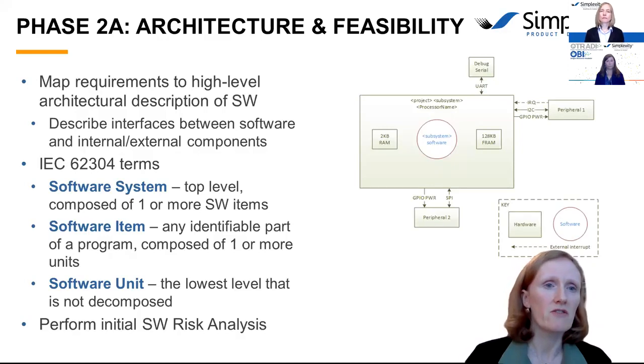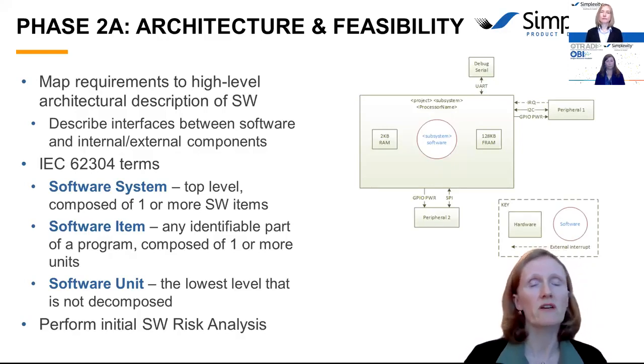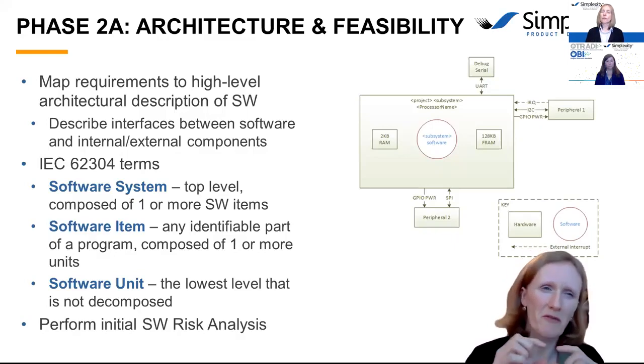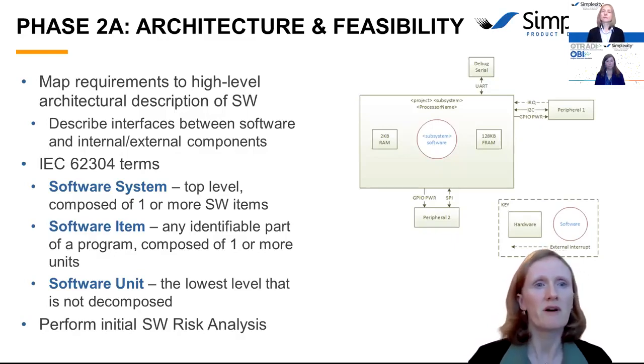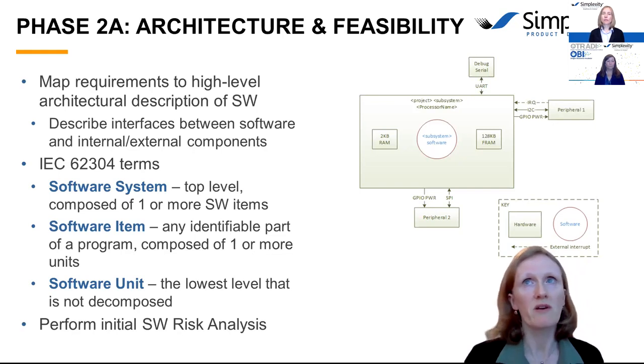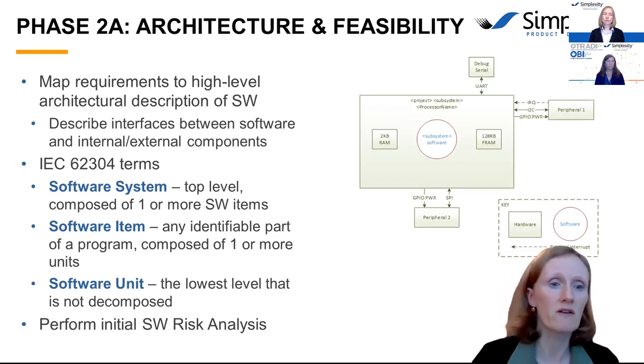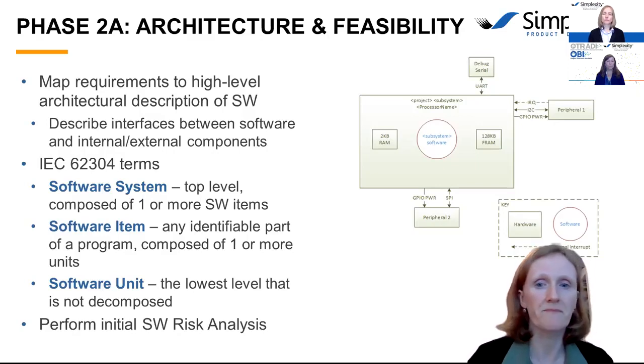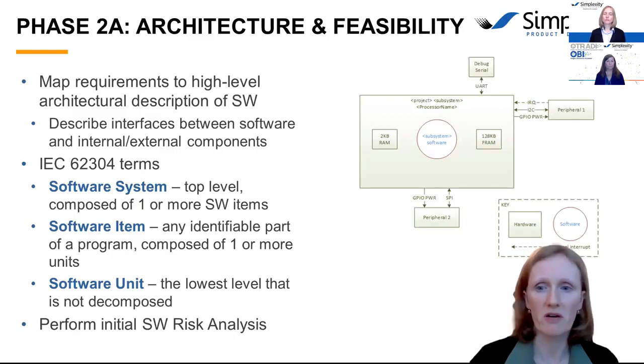But it can get a little confusing because a lot of times in the software industry, we talk about unit testing and we're talking about function-level testing. But for medical devices, the software unit doesn't have to be down at that level. You want to think about what is a logical unit, and also know that, depending on your classification, it could be required to do software unit testing. So you want to pick a level that's appropriate for doing that type of testing. And these terms I'm going to use later, so keep those in mind.